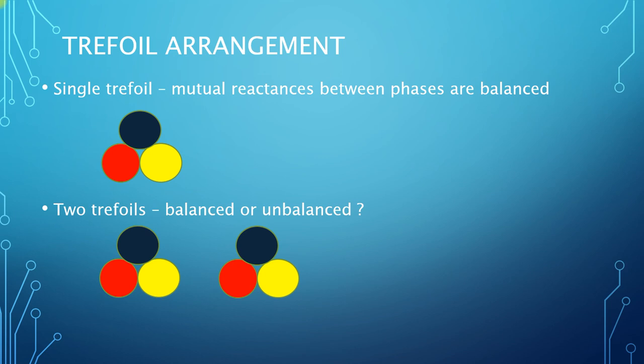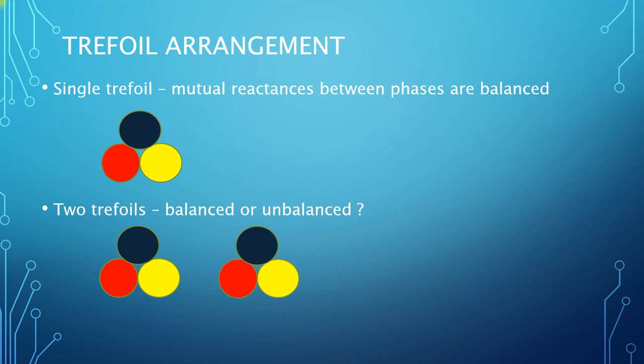Another way of arranging single-core cables is to adopt the trefoil arrangement, where the cable centres are placed at the corners of an equilateral triangle. If we have a single trefoil arrangement, then it is clear that the mutual reactances between the phases will be balanced. If we have two trefoils which are themselves individually balanced, will the overall circuit comprising the two parallel three-phase circuits be balanced or unbalanced? Will currents circulate between the two individual trefoils? This was the question which originally motivated me to look at this issue.